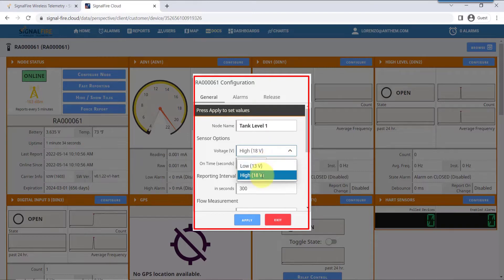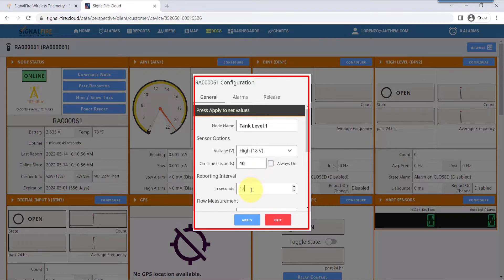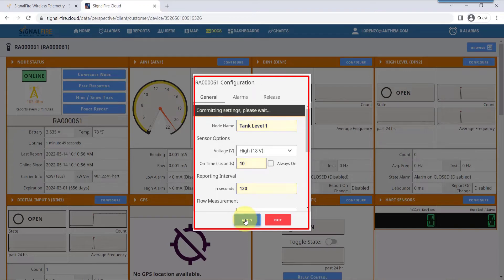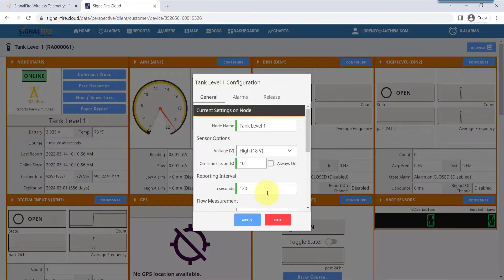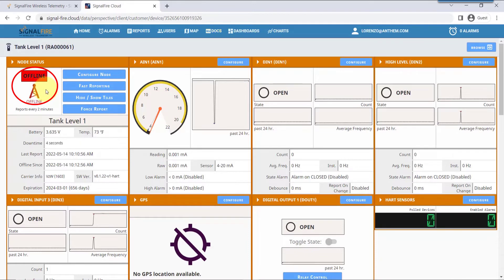Then set up the right voltage for the transmitter. Look at the specification of your transmitter for the voltage and the duration that is required to activate and power your transmitter. Finally, how often you want to measure the sensor to the cloud. Hit apply. Once the device returns green or the web app returns green, that means the changes have been sent to the Ranger. You'll notice the Ranger will reboot and go offline for a couple seconds.